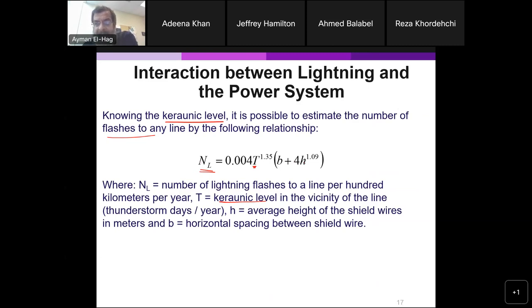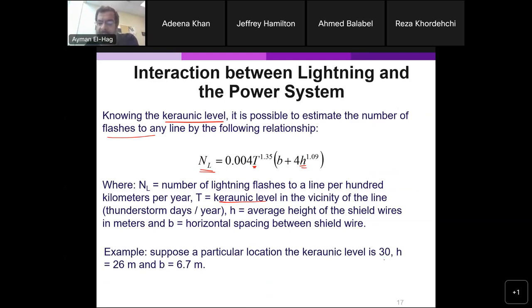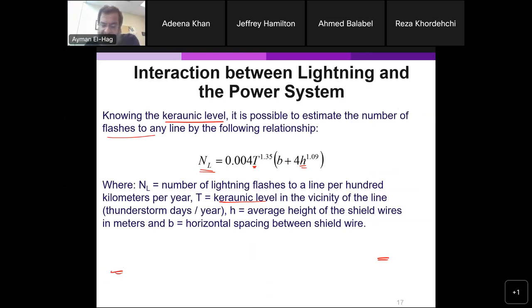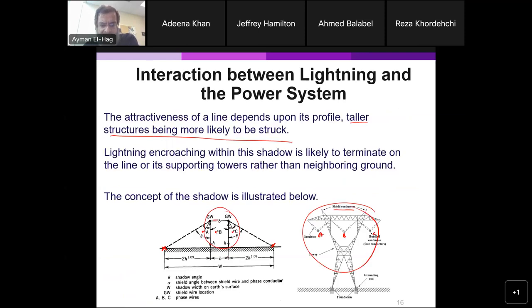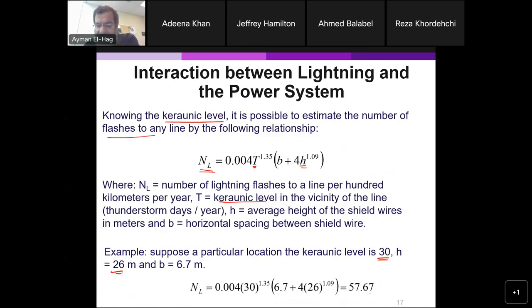Times B plus H. B is the distance, so the bigger the distance, the more the protection. And the higher the H, again, that means you have a much bigger area where, if the lightning hits, it will most likely hit the structure. So for example here, the keraunic level is 30, H is 26, and B is 6.7 meters. Let's remind ourselves what those values are. This is your B, this is your T, this is your H. H is basically the length of your tower. This is how to decide your W, which is 2H^1.09 plus B plus 2H^1.09. H is basically the height, and it makes sense that the taller the structure, the more likely you will have a flashover on those structures. So here you will have 57.67 per 100 kilometers per year as the chance of a flashover.